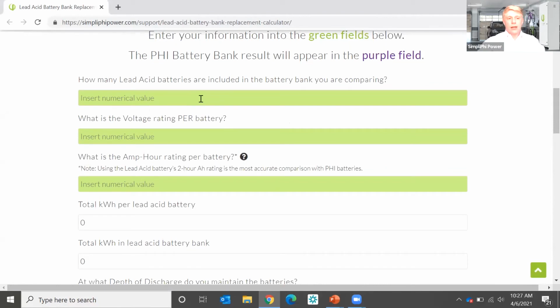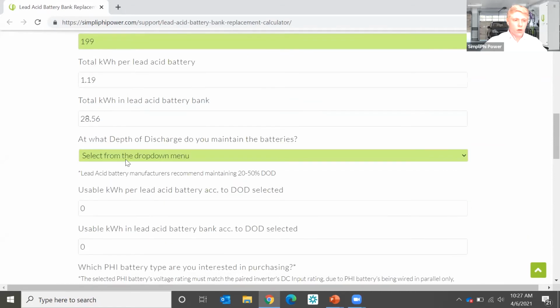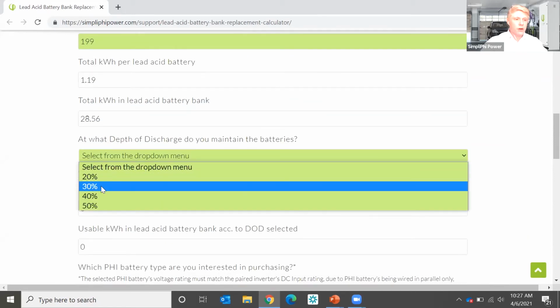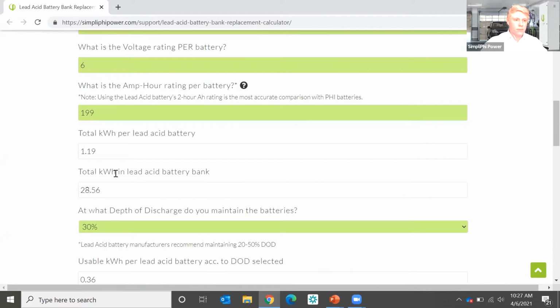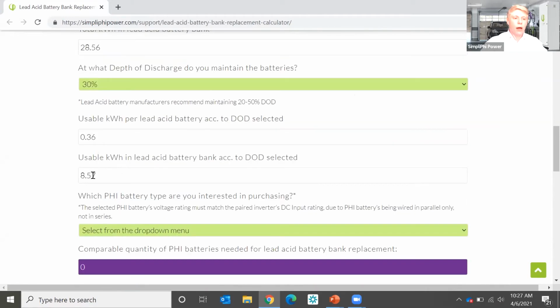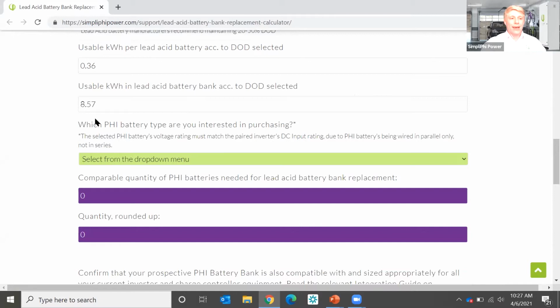I'm just going to enter an example of a lead acid system here. Let's say we've got 24 six-volt batteries, arranged in 3 strings of 8 for 48 volts, and they're 200 amp hours per battery. I'll estimate you're using them at 30% depth of discharge, which leaves you with just under 9 kilowatt hours of usable energy in that bank. That capacity will also decrease if you're pulling at high discharge rates, and lead acid batteries are less efficient as well.